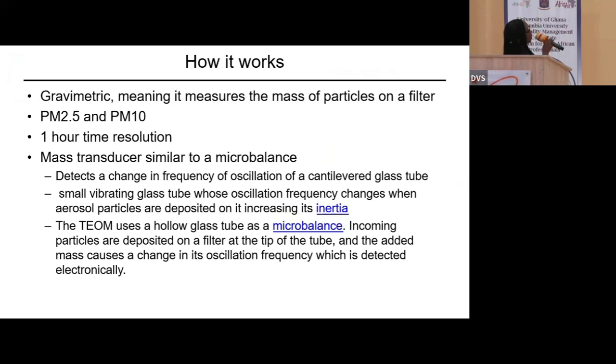So reference monitors work by gravimetric measurement, and it's a 1 hour time resolution. Using a microbalance, it detects the change in frequency of oscillation of a cantilevered glass tube. It's a small vibrating glass tube whose oscillation frequency changes when aerosol particles are deposited on it, which increases its inertia. If you have one particle going in, the change in frequency is low.